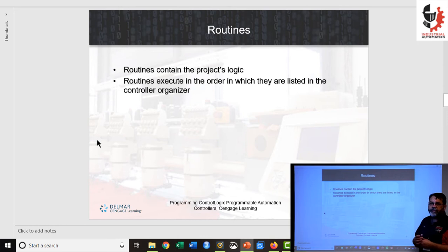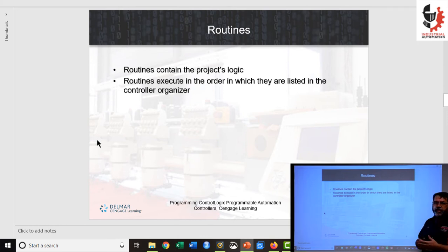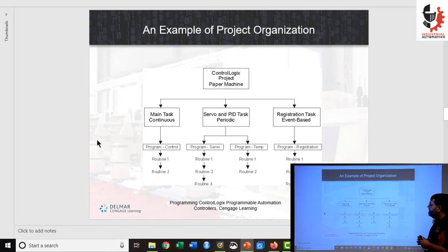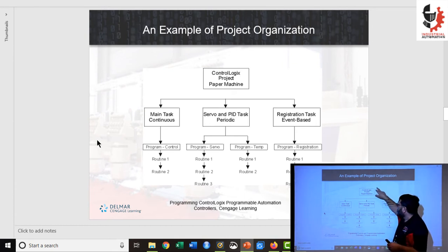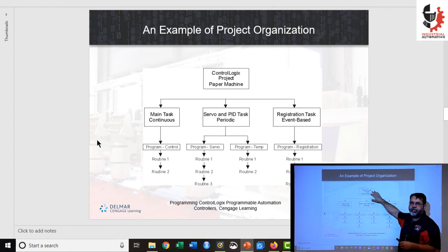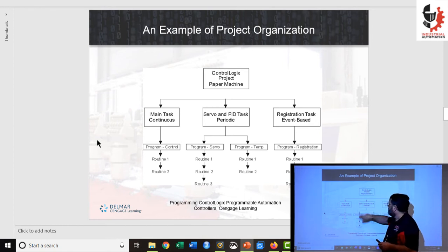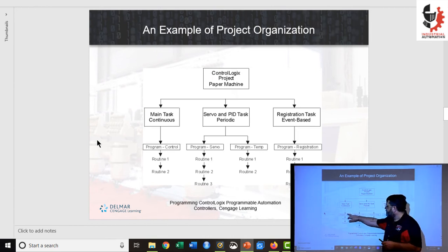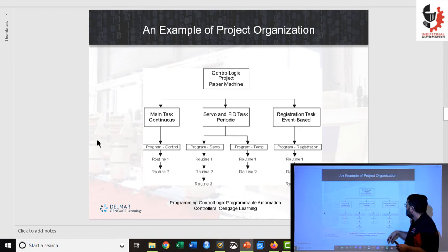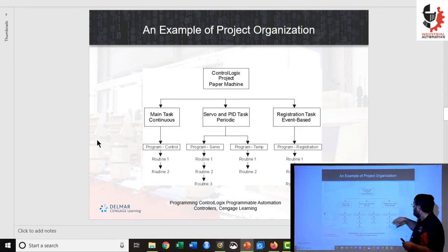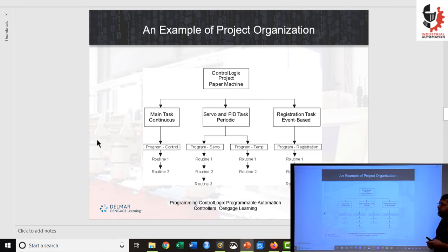The routine is where you put your logic, whether you're doing ladder logic, structured text, or some other language. Here's a project example: our main project contains all of our programming. Inside this main project we have our continuous task with one program that has two routines, a periodic task, and an event-based task. That's one way a project can be set up.